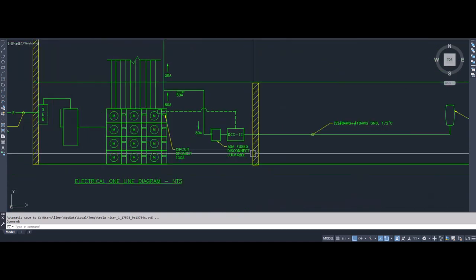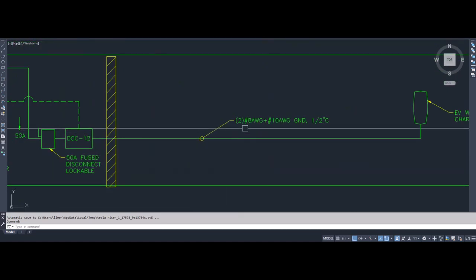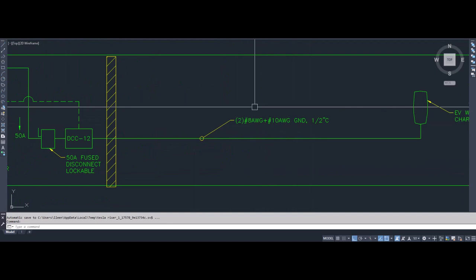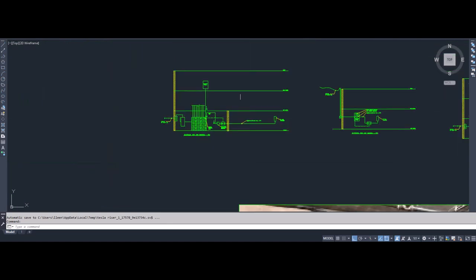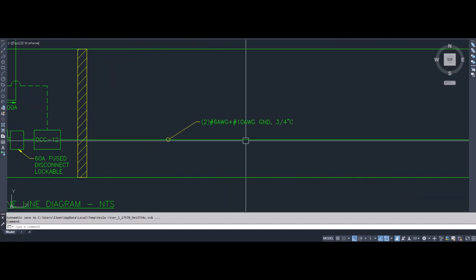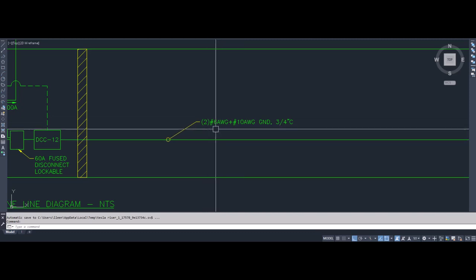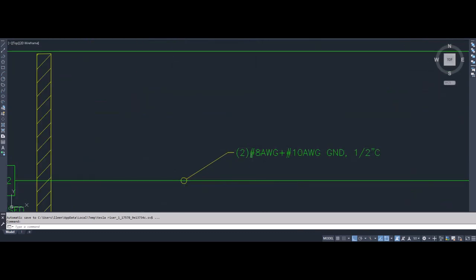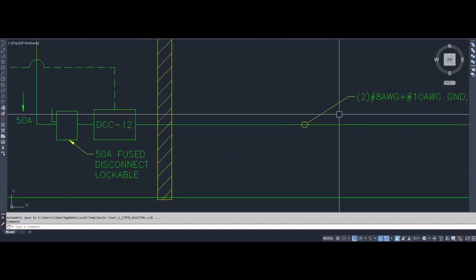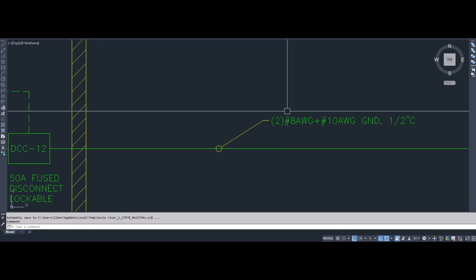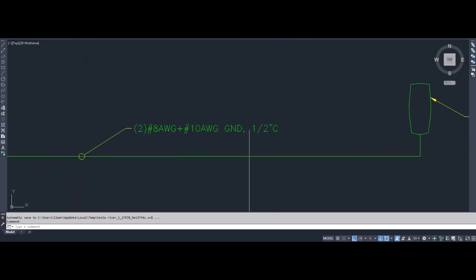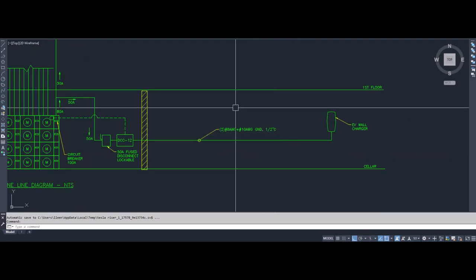Now for a 50 amp, it's going to be a little bit different. The wire size can be a little bit smaller. So it's going to be an 8 rather than a 6, right? Because the higher the number, the smaller the wire. It works the opposite way than the number size. So in this case, for a 50 amp, the wiring decreased to an 8, and then you can use a 1/2 inch conduit.